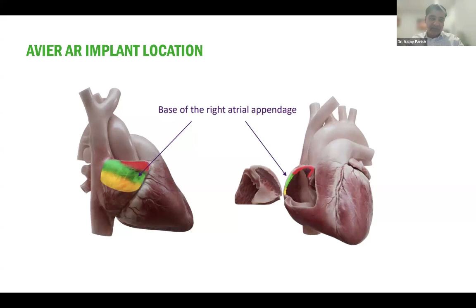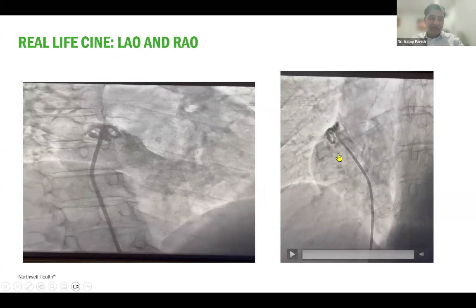This is one of the venograms or appendograms, where in RAO it identifies the right atrial appendage, but in LAO it gives you an idea of the lateral wall, and this way you can define your target location. You can either use a pigtail or you can use the sheath itself. The atrial Aveir sheath and ventricular Aveir sheath have a protective sleeve, and it gives the extra option of doing such a thing, unlike Micra devices where the cup is slightly sharp compared to this protective sheath.